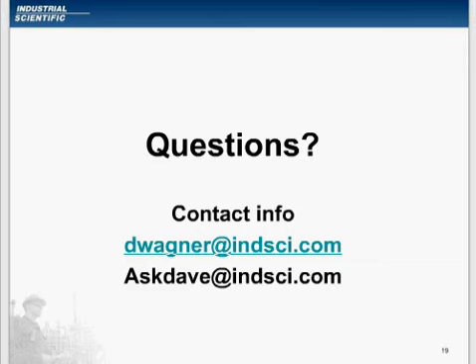If I told you it was going to take 10 minutes to bump test your instrument, you'd probably tell me I was nuts and you were never going to do it. Nevertheless, in figuring out the cost in this way, that's the number that I used, and a cost of time of $30 per hour, and that works out to about $106,000 for a fleet of 1,000 instruments. And again, that number is very conservative, and it's probably pretty heavily overstated.